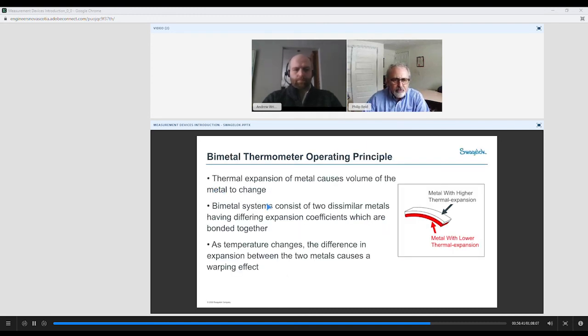A bimetal thermometer works on the effects of expansion and contraction of two metals. So you have two different metals: the metal with the higher thermal expansion and the metal with the lower thermal expansion. The bimetal system consists of the two, and they're bonded together.